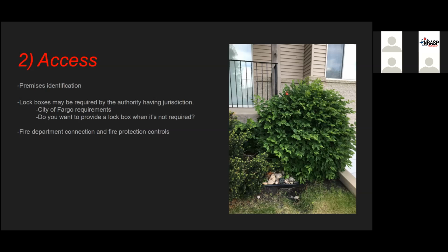Fire department connection. Now I've got this picture up on the screen because you can kind of see behind that bush there's something red. That is actually a fire department connection. So if there is a fire in this structure, we would connect our fire hoses to that fire department connection and supplement the fire sprinkler system. Now, my guess is we are probably not even going to know that that fire department connection is there most of the time because it's covered behind that bush. So access is important to things like our fire department connection. Make sure there's nothing blocking it, a bush, no storage placed in front of it.